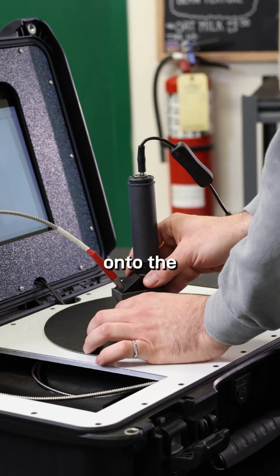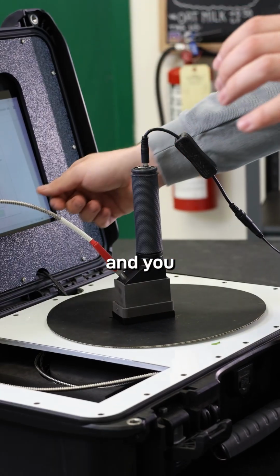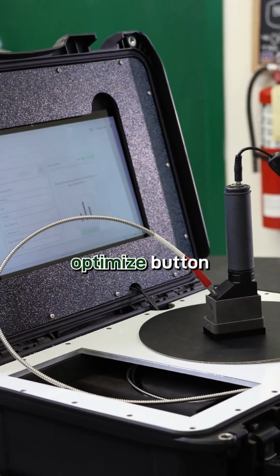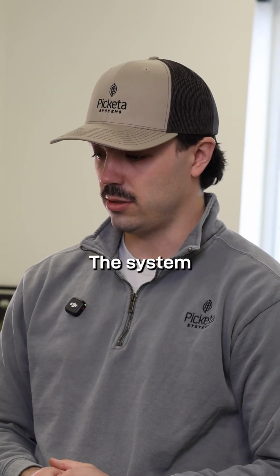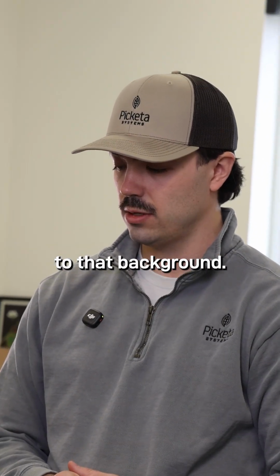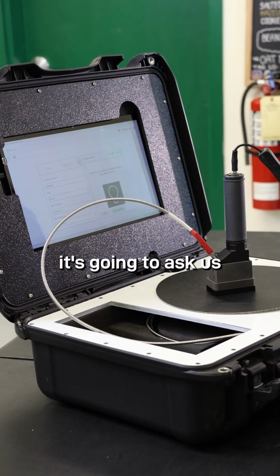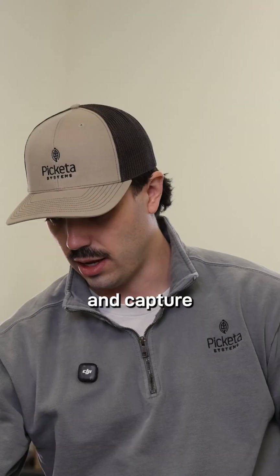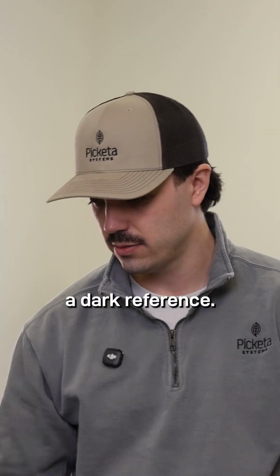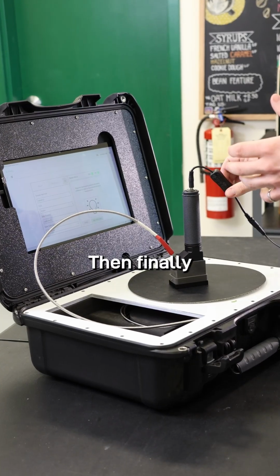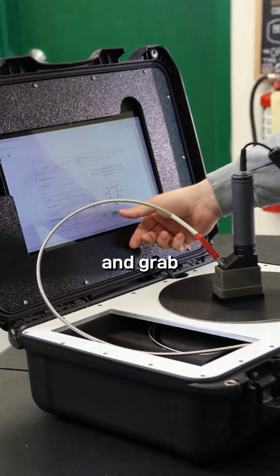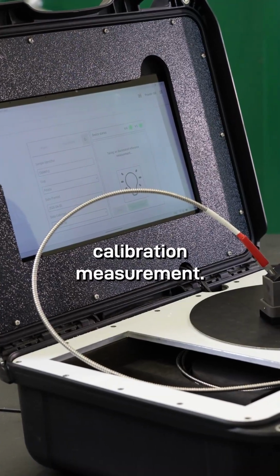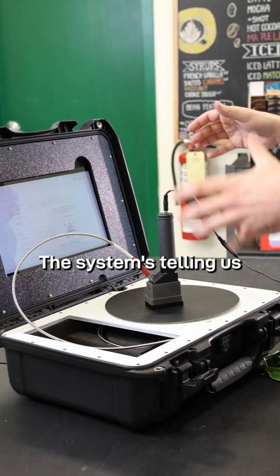You place the probe onto the white background and you click on the Optimize button to grab your first calibration measurement. The system is going to get calibrated to that background. Once that's done, it's going to ask us to turn off the probe and capture a dark reference. So we'll do that. Then finally we open up the probe again and grab a final calibration measurement. All right, there we have it. The system's telling us it's ready to go.